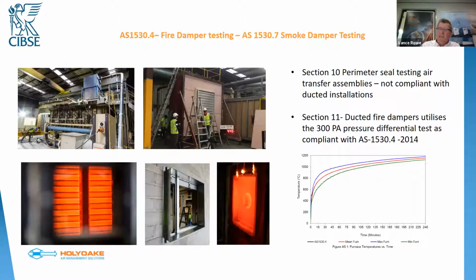That was at about just over 1,000 degrees, about 3.5 hours into the test. It was pretty warm, I might add. The one in the middle down the bottom is that multi-section damper with the mullion in it. The graphic on the right is actually a circular fire damper in the test wall after it had been removed from the testing furnace. And obviously we were having a look at the damper and how it looks on the back. I can tell you that looking at some of the gyprock that comes out of those furnaces, it really does blow your mind in terms of how good some of those products are out there.